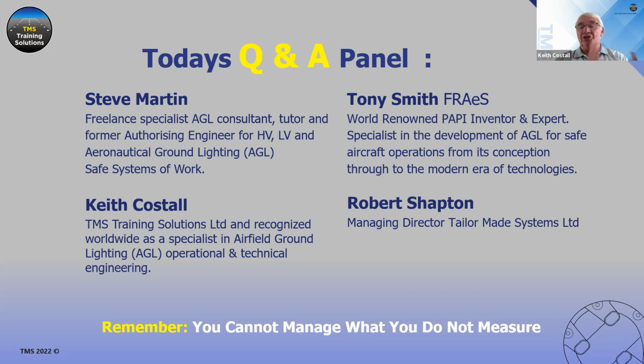So do you attach a new technology LED light fixture to a thyristor base, or do you change them both together so you have an IGBT CCR and an LED, or is an IGBT CCR okay for tungsten halogen? So there are these interface issues that exist. One is that light fixtures and CCRs use pulse width modulation technology, and that area has created a lot of discussion and is ongoing.